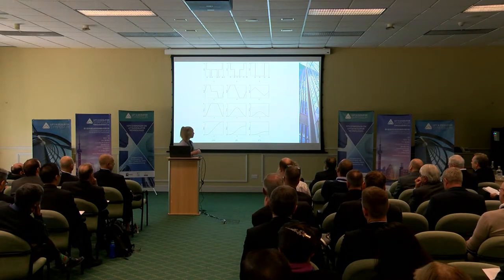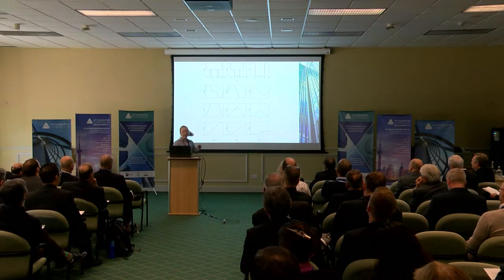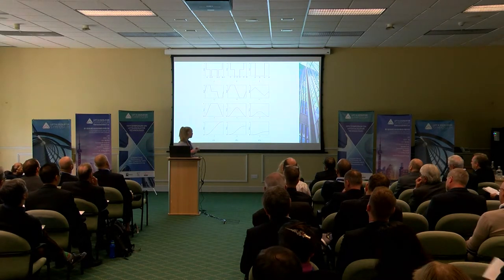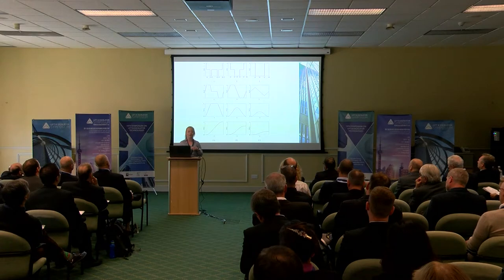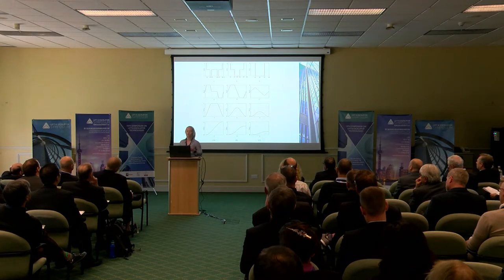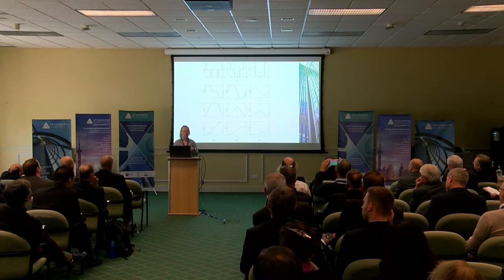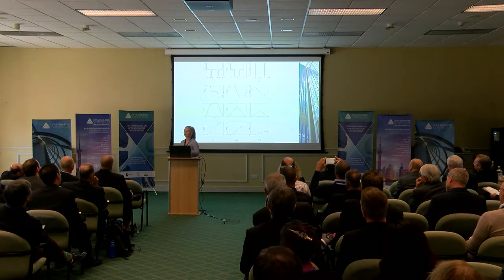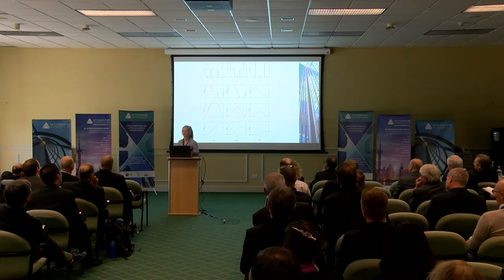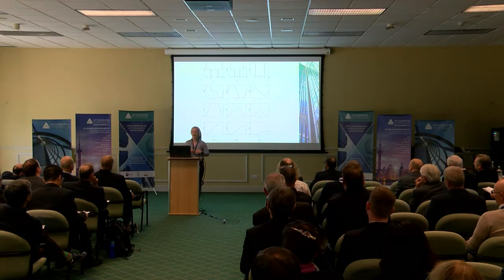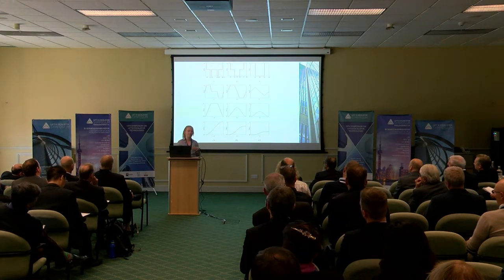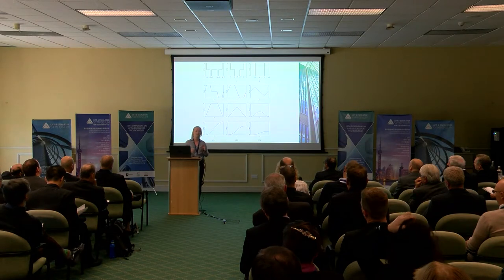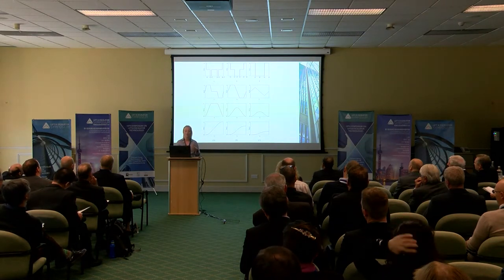The rows shown here are the jerk, acceleration, velocity, and displacement profiles for the three possible scenarios of lift motion: the first being the lift reaching full speed, the second being the lift reaching full acceleration but not full speed, and the third with the lift reaching neither full acceleration nor speed. For the purposes of the project, it was necessary to model each trip as accurately as possible. Modern variable speed drives, which control the lift's motion, can be programmed to match the ideal lift kinematics curves very closely. It was therefore decided that the best approach was to fit the measured data to these idealised kinematics plots. A clear understanding of the shape of the curves is what's essential.